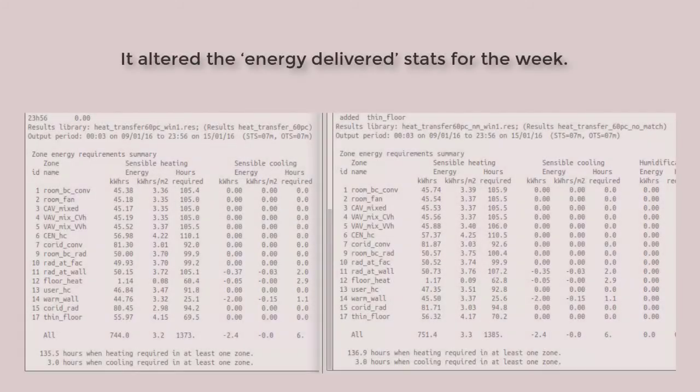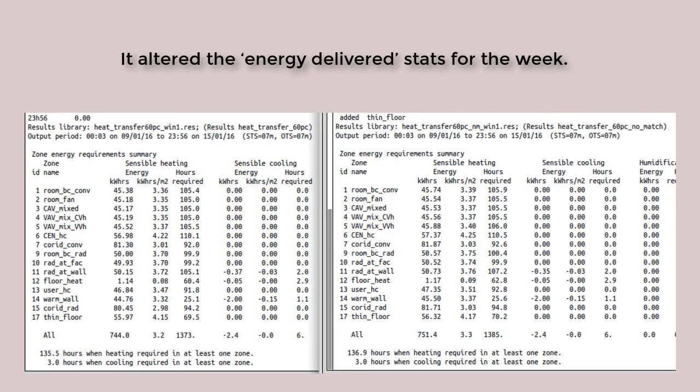Did this make a difference? Well, let's aggregate the heating and cooling delivered into the occupied spaces with and without the temperature matching control. Yes, there is a difference. It's not particularly earth-shattering in this model. In another model, it might be noticeable.